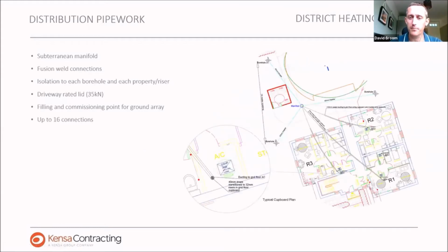Next slide. This shows schematically a typical installation where we've linked 3 boreholes together and distributed out to 3 heat pump locations. This one was a new build, so we could go under the slab of the building. On retrofit, we'll generally come up surface mounted, either on the outside wall, or sometimes up to roof level through soffits and then drop down into cylinder cupboards. The benefit of having all the distribution on the ground side is flexibility in how we connect these heat pumps together.